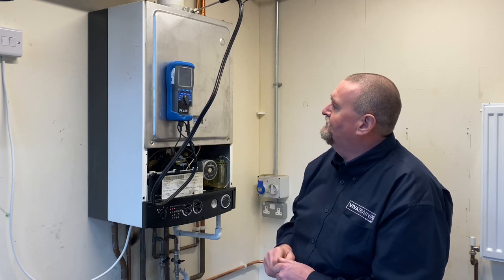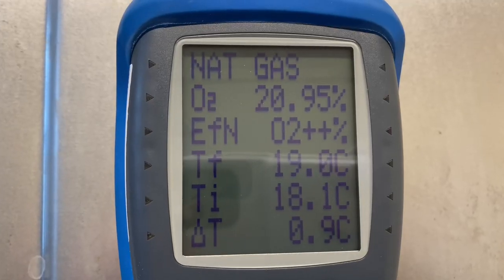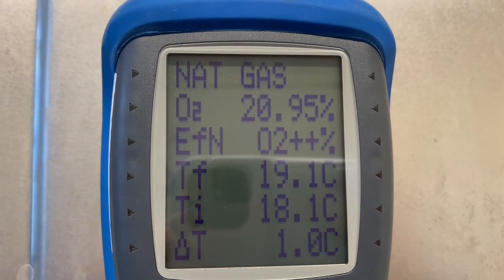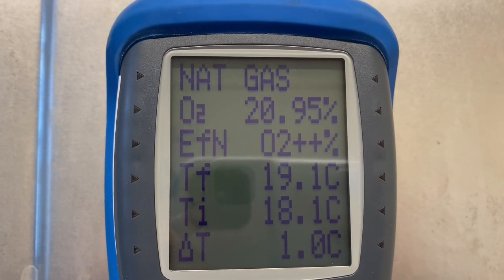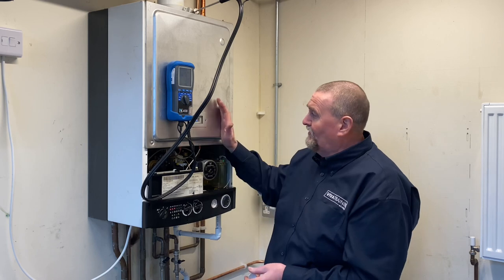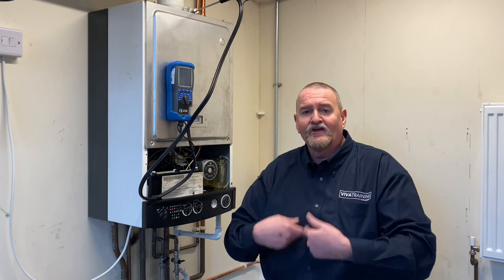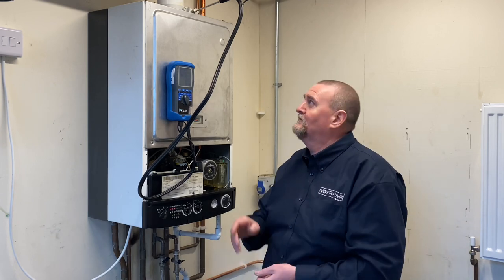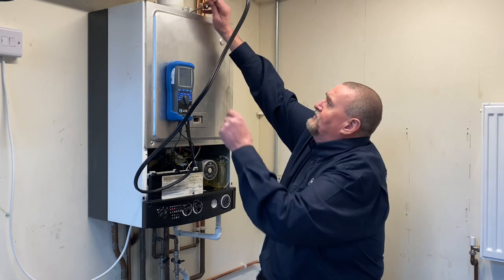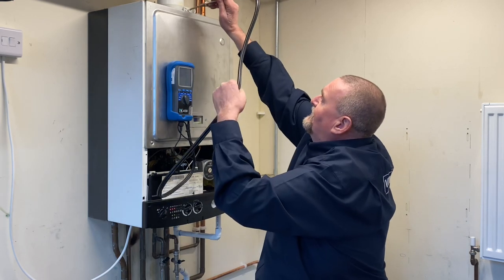I've moved the analyzer across to O2. The O2 figure I'm looking for is somewhere about 20.6 - this is reading 20.9, so I know it's breathing nice clean fresh air. I've got the boiler running because if it wasn't running I'd obviously get clean fresh air coming through, so I'm checking to make sure I've got no cross-contamination. The next thing I'll do is move across and do the flue gas analysis.